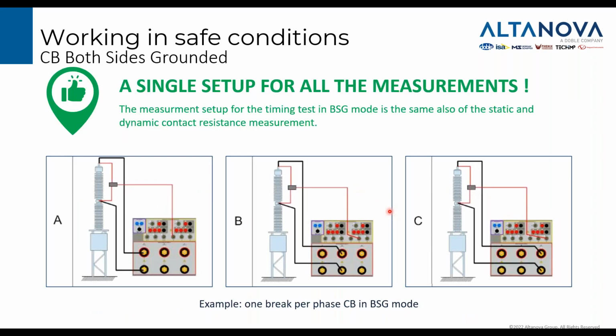With the CBA 3000, you can perform the test in both sides ground mode using exactly the same wires, the same connections that you are using for the resistance measurement. So with the CBA 3000, when the circuit breaker is grounded on both sides, you don't have to make any change to the connection. So it makes the life of the operator even easier and still faster.